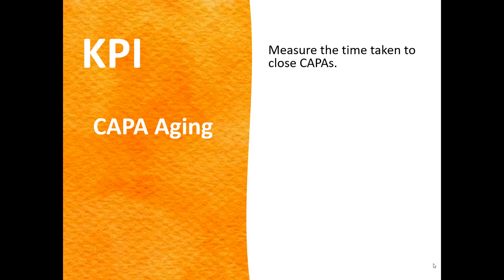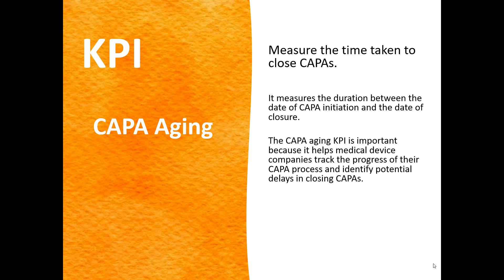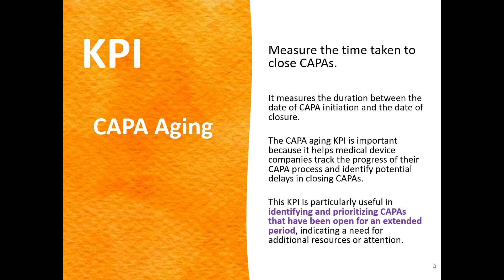Another KPI would be CAPA aging — the measured time to close a CAPA. For your CAPAs that are being closed, how long is it taking to close them? It measures the duration between the date of CAPA initiation and the date of closure. You want to be closing your CAPAs as quickly as possible. Obviously, you don't close them unless you've done all the work required, but you still want an efficient system. If CAPAs are taking a very long time to close, you might need to put more resources on them, or figure out why — for example, perhaps people in your organisation don't have the right problem-solving skills to get to the root cause.